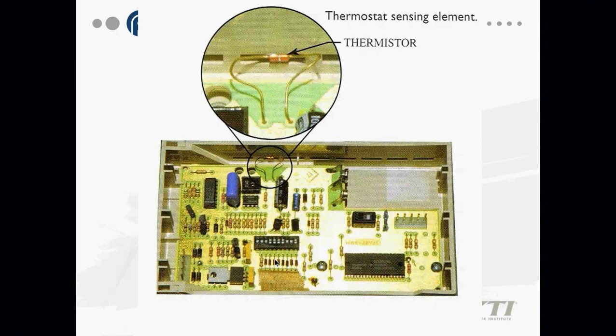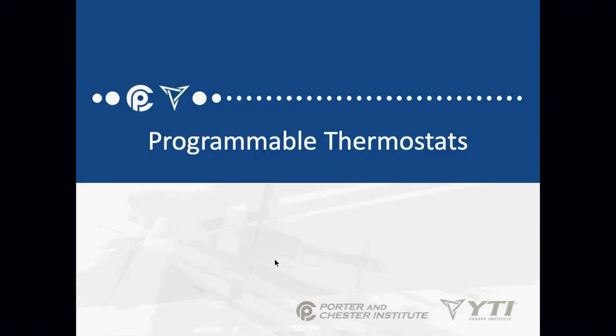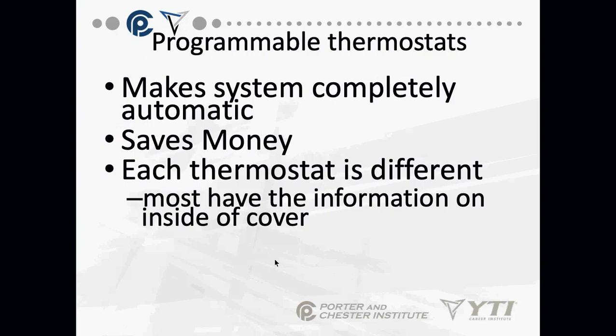Okay, the thermostat sensing element in a digital thermostat is a thermistor. It's just a device that changes its resistance based on the temperature. Okay, programmable. Make system completely automatic. I don't want to spend a ton of time on these because basically this is the default standard right now. Okay, if you look on the inside of the cover of a programmable thermostat, it has a lot of times a code for how you get into the installer setup of the thermostat.